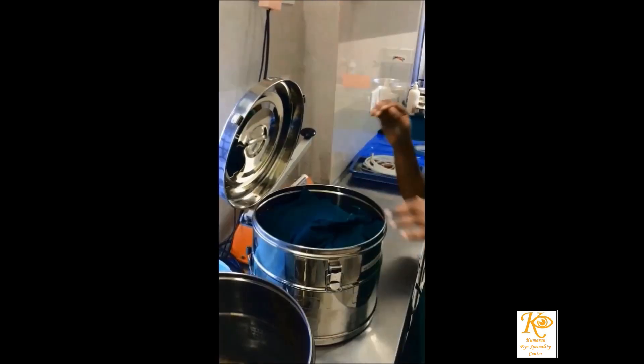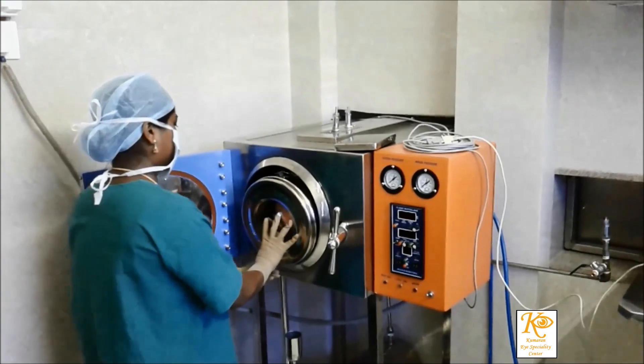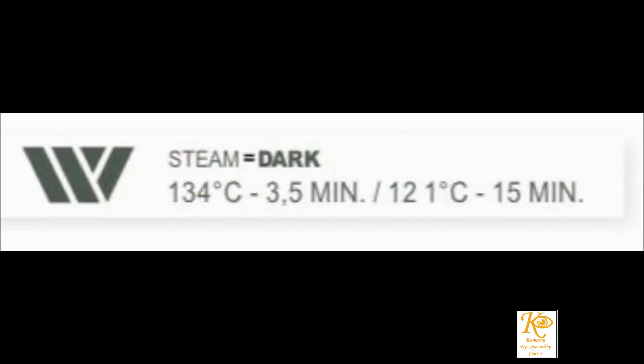The Helix PCD test works on the principle that pre-vacuum autoclaves have to remove the air in the tubes and allow the saturated steam to pass through the lumen of the spiral tube to reach the indicator kept in the plastic casing. Hence, this test ensures adequate air removal and also checks the ability of steam to penetrate hollow instruments.